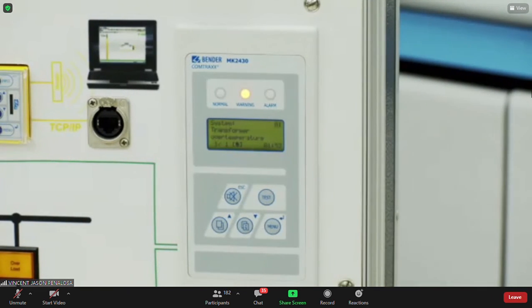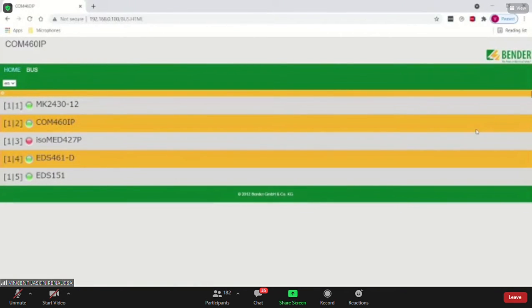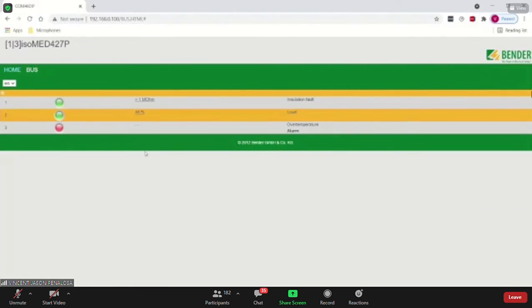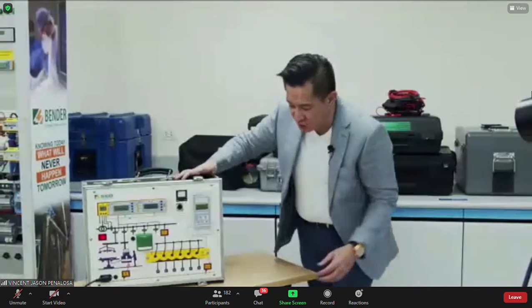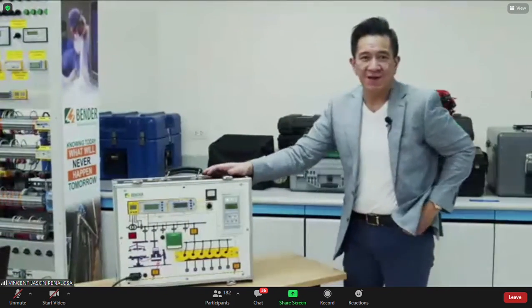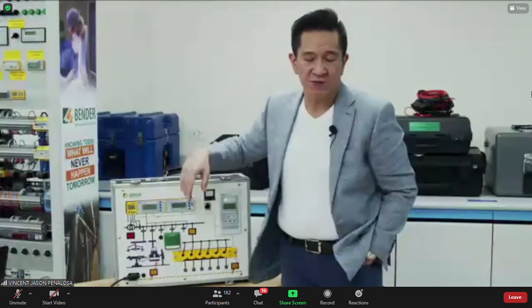So if I switch myself to the monitoring system, as you can see here, I have the ISOMED. That's the insulation monitoring device. If I click on that, it will tell me that my insulation resistance is fine. I still have greater than 1 mega ohm. My initial load was about 44%. And then the next one is over temp. I hit over temperature. So why did that happen? I can turn that off. As you will see, if I start turning this off, even if I turn off the fault, the alarm almost never goes away. What I programmed is, if I turn off the alarm, it turns off. But generally, it is already stored inside the system as a fault.